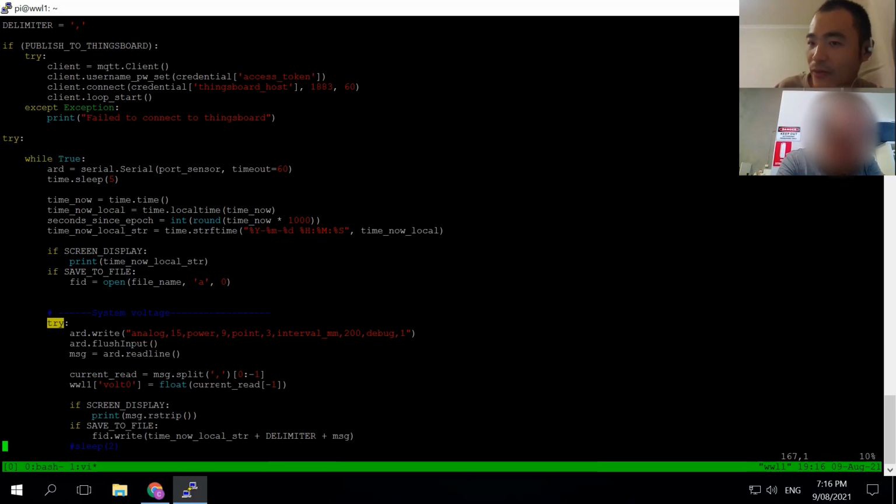One of the things that we ask the system to do is to reboot every day. This reboot is the same as pulling the power from the board, not just a soft reboot. We feel this is extremely important, particularly when you have a Raspberry Pi, which is a computer. The computer might be booting, but the booting failed.